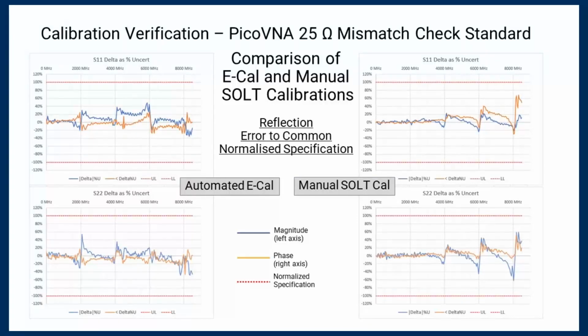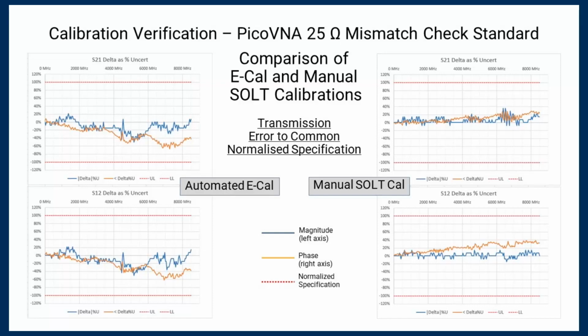Frankly, I think all of us would have liked the manual calibration that we perform to have beaten the automated calibration hands down, but that certainly isn't the case here. These two measurements, based on automated eCal and manual cal, are very similarly placed within their specification bounds, and it's the same specification in both cases. Looking at the transmission parameters, I think I'd argue that the manual calibration did a little bit better here, but the eCal is also within specification.